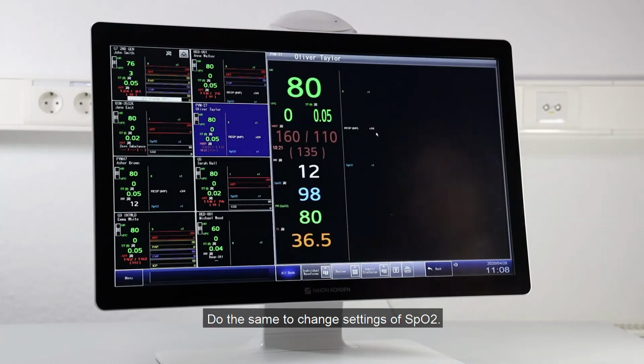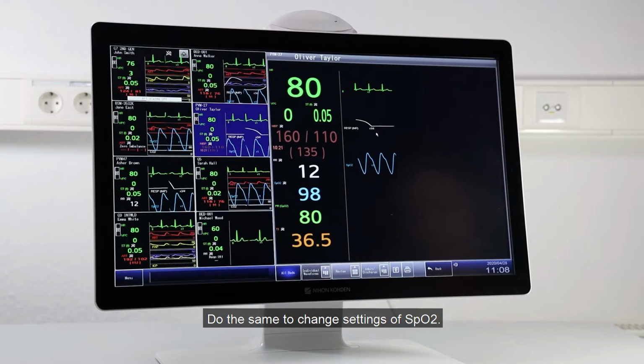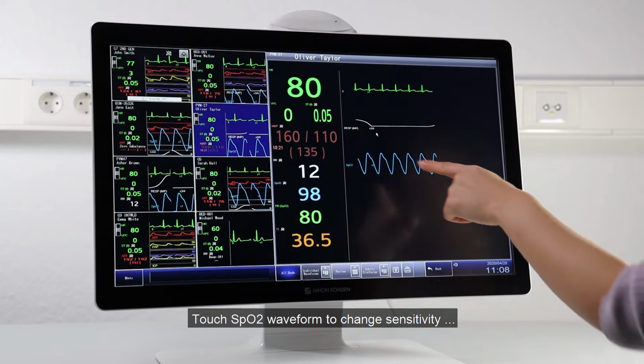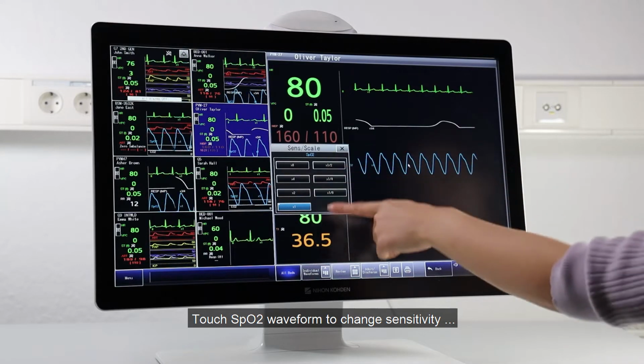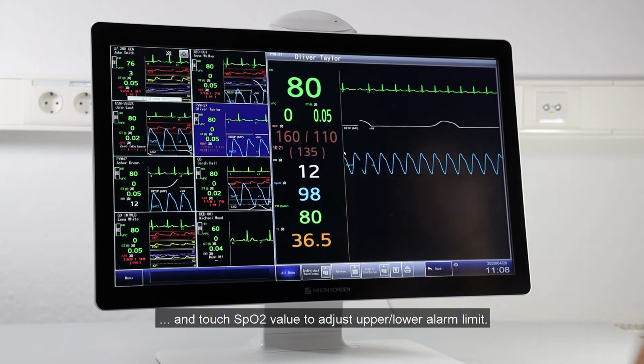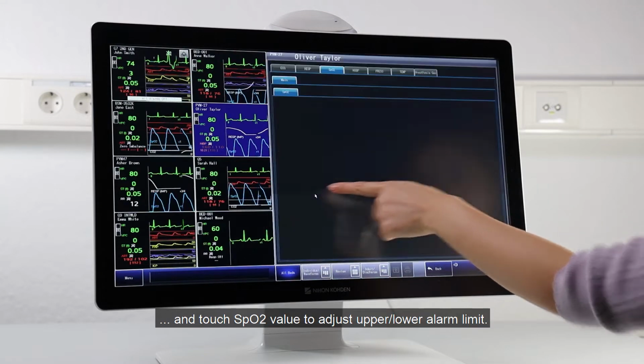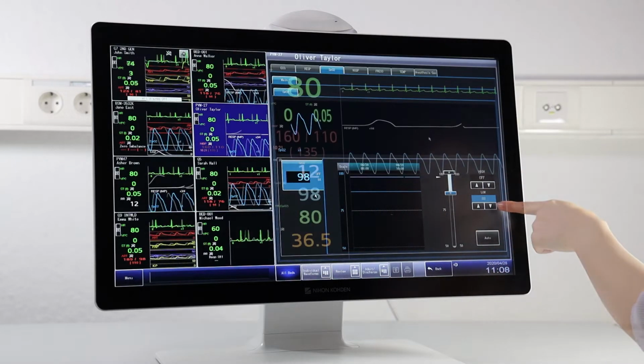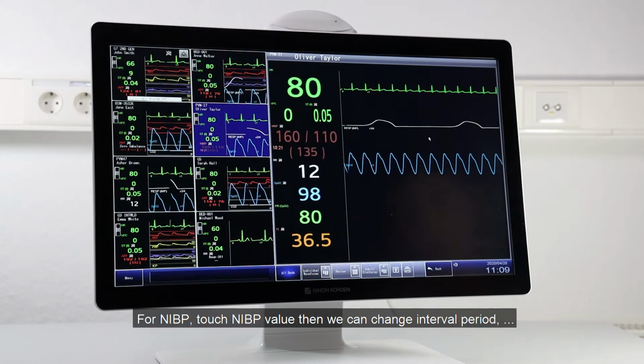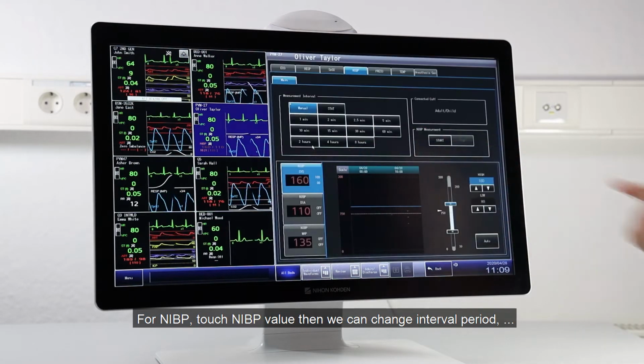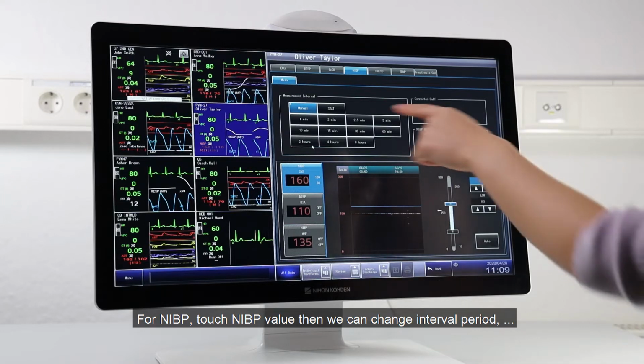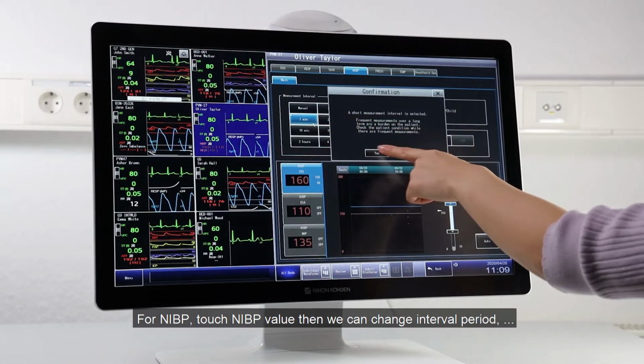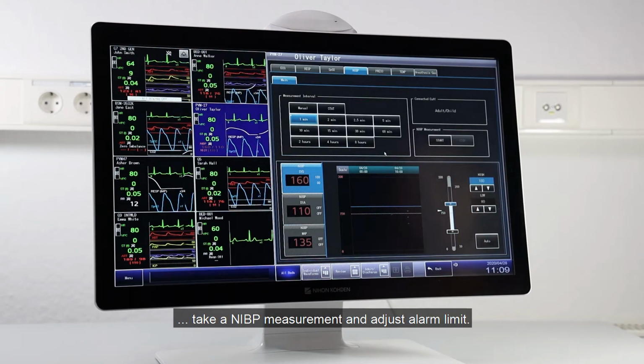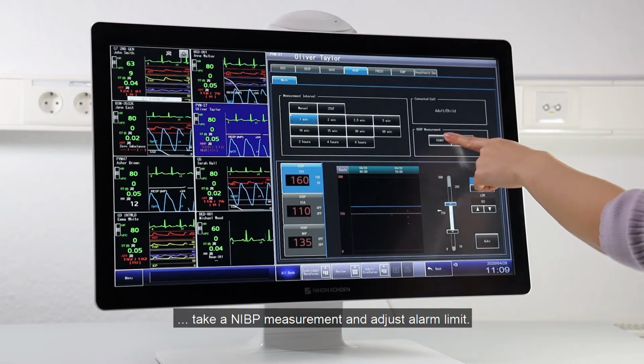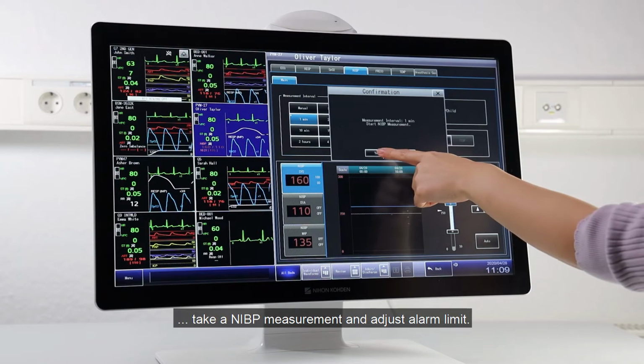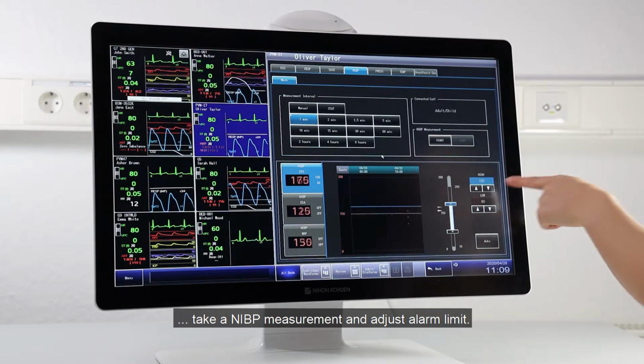Do the same to change the settings of SpO2. Touch the SpO2 waveform to change sensitivity, and touch SpO2 value to adjust upper-lower alarm limit. For NIBP, touch NIBP value, and then we can change the interval period. Take an NIBP measurement and adjust the alarm limit.